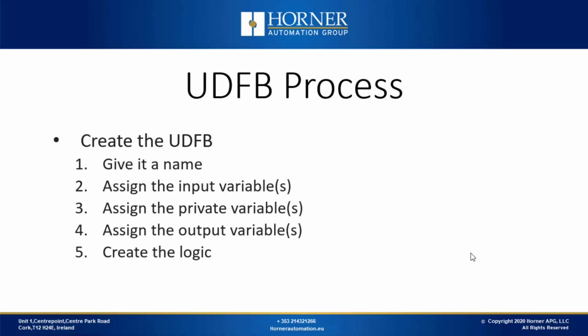The process of creating a UDFB is made up of 5 steps: naming it, assigning input variables, assigning output variables, assigning private variables, and creating a logic. During the creation of your logic, if you find you need to assign additional variables, you can do so, as this is an iterative process.